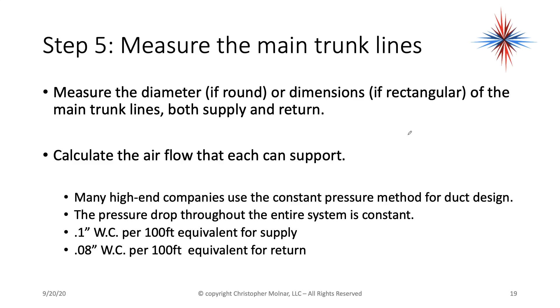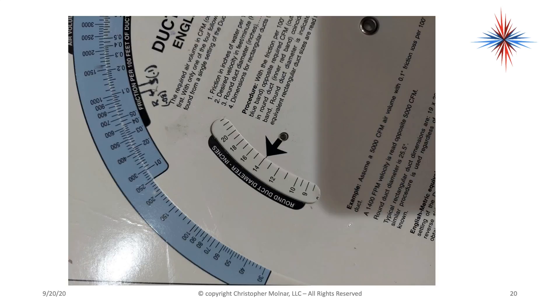Many high-end companies use the constant pressure method for duct design — the pressure drop is equivalent through the entire system. Most of us use 0.1 inches water column per 100 feet for the supply, and 0.08 inch water column per 100 feet equivalent for the return. Be careful — this is not 100 feet of actual duct work. It's the equivalent, taking into account items like 90-degree elbows. A 90-degree elbow could equal 25 feet of duct work. We use lower friction loss for return because of filter efficiency.